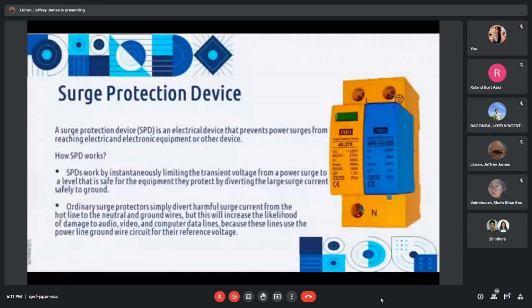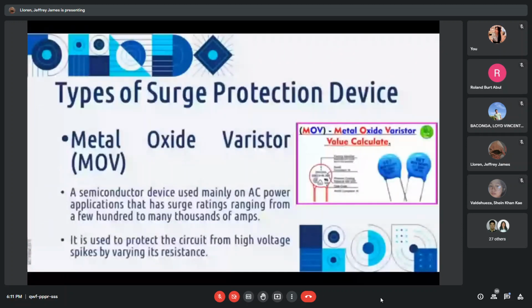So more sophisticated surge protection technology is designed so that unwanted voltage is not passed through protected equipment via power, telephone, or other cables. They can prevent excessive energy from reaching sensitive parts of equipment or systems by disconnecting signal lines and diverting surges to earth. Once the surge current has subsided, the advanced SPD automatically restores normal operations and resets to a state ready to receive the next surge.